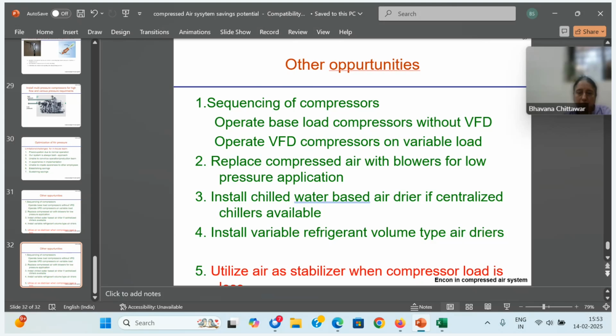Replace compressed air with blowers for some applications where low pressure is enough. You can install chilled water based air dryers wherever chilled water is available from the chillers; a separate air dryer is not required. Then install variable refrigerant volume systems; there are VRV system dryers available in the market. Then the last point, utilize air as a stabilizer when compressor load is less.